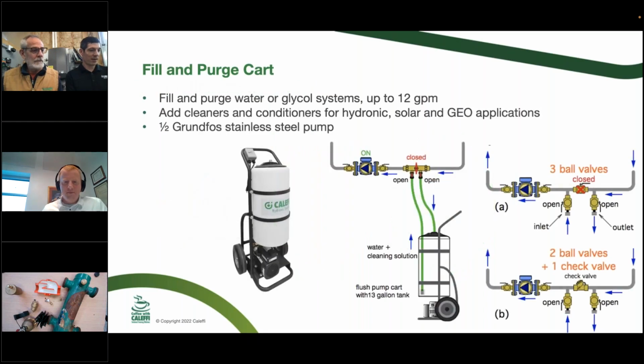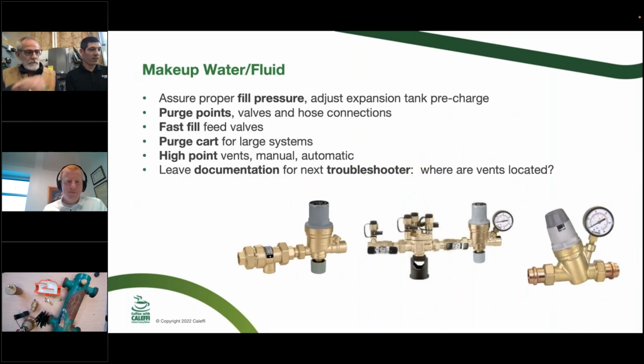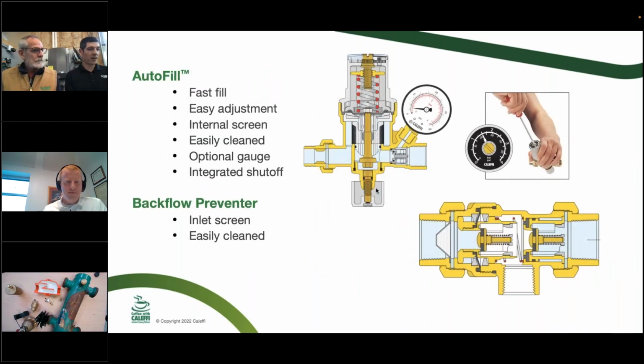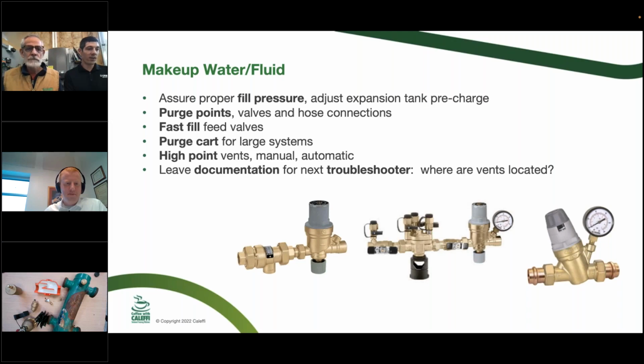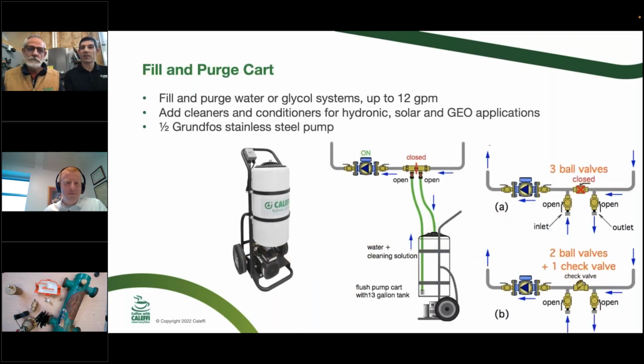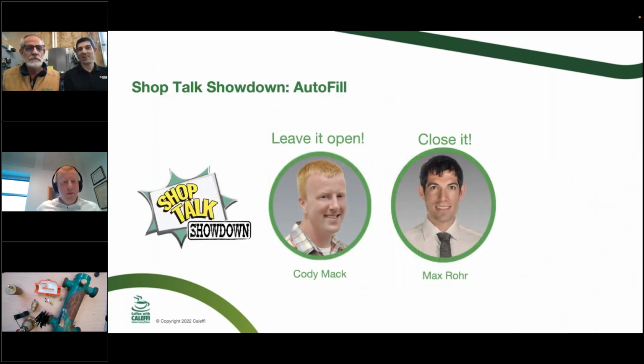I'll back up a slide here. The AutoFill has this nice gray knob on the bottom that you can tighten up, and it's going to close the fill valve. It's going to prevent it from filling automatically after you've got your system up to temperature and up to pressure. Cody's going to argue that you should leave it open. So Cody, tell me why leaving it open is a good way to go.